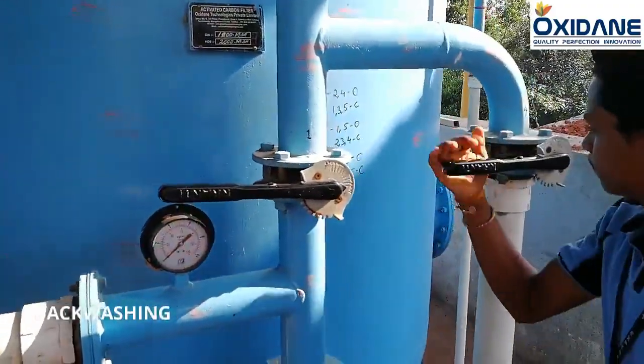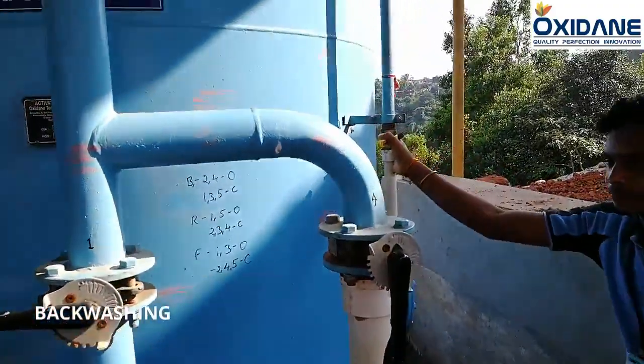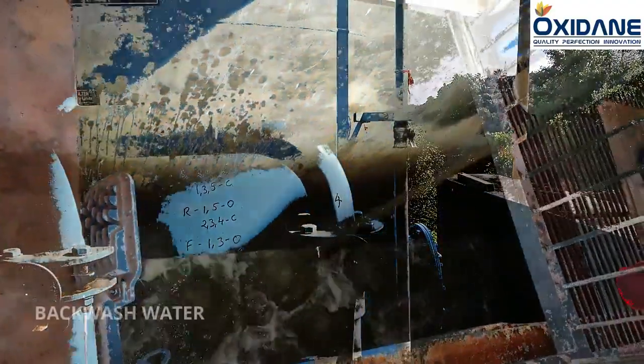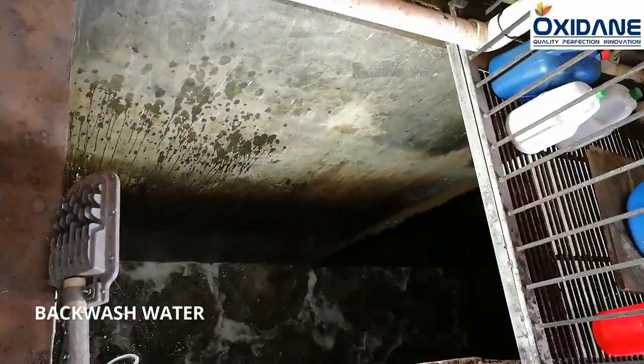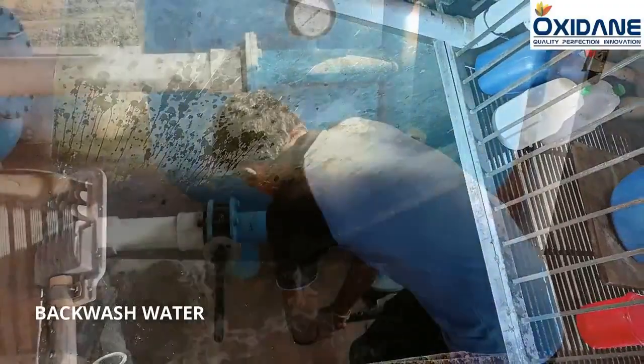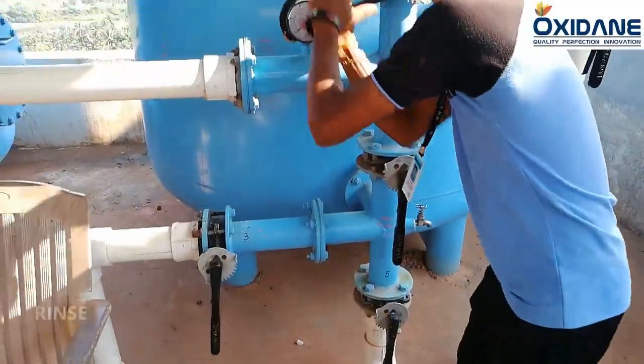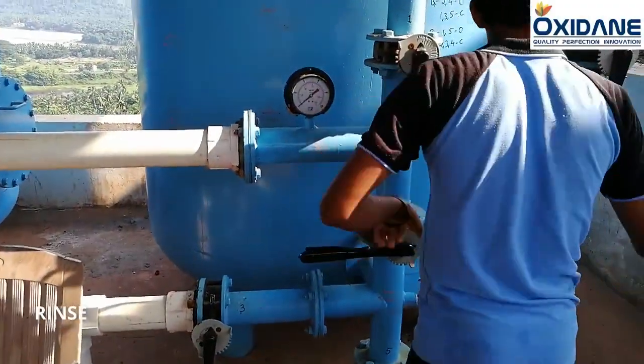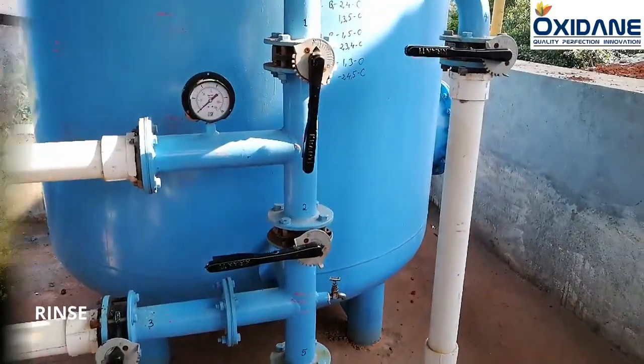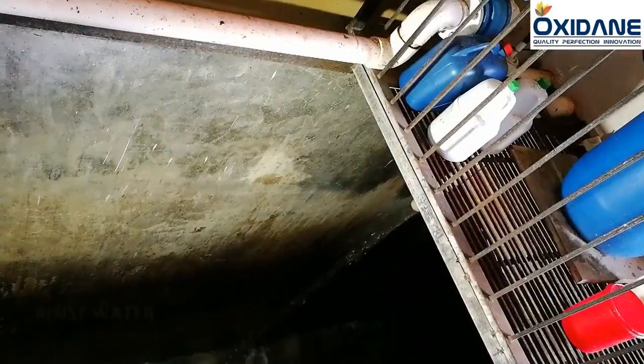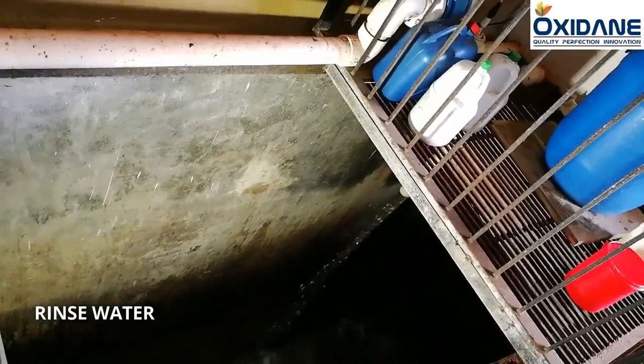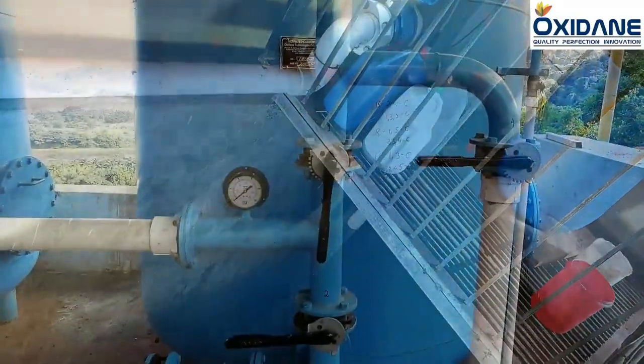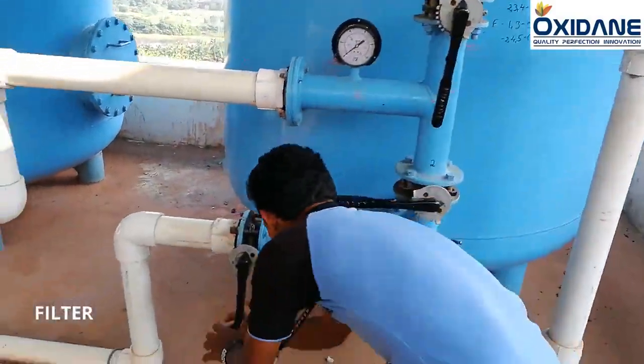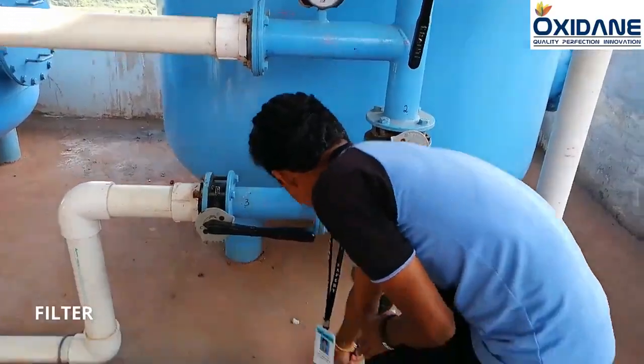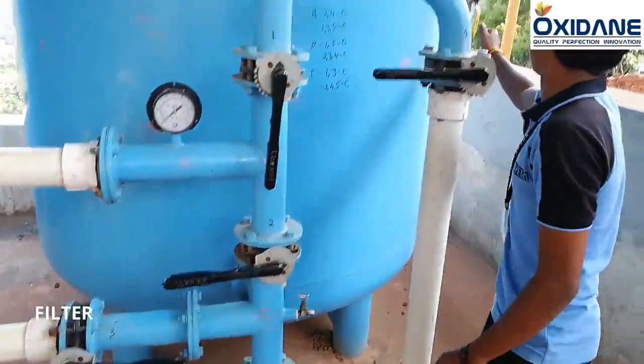Backwashing. The filter is then taken out of service and cleaning of the filter media is effected by flow reversal, also called backwash. To assist in cleaning the bed, the backwash operation is sometimes preceded by air scouring by way of agitation through the underdrain system. The air scouring agitates the sand with a scrubbing action, which loosens the intercepted particles. The filter is now ready to be put back into service.